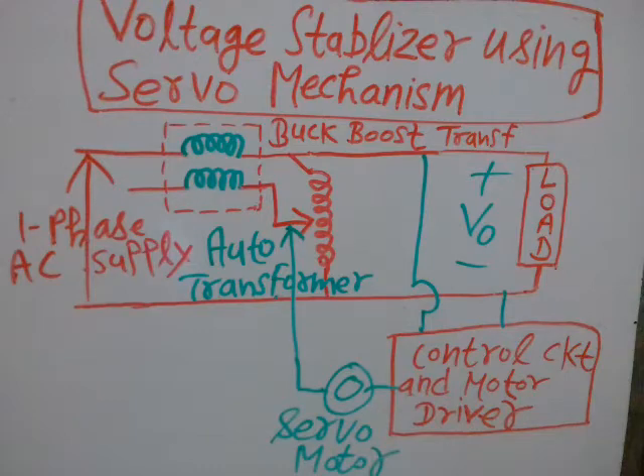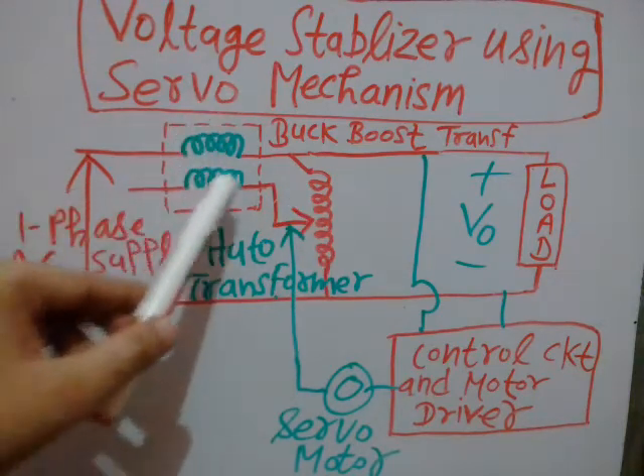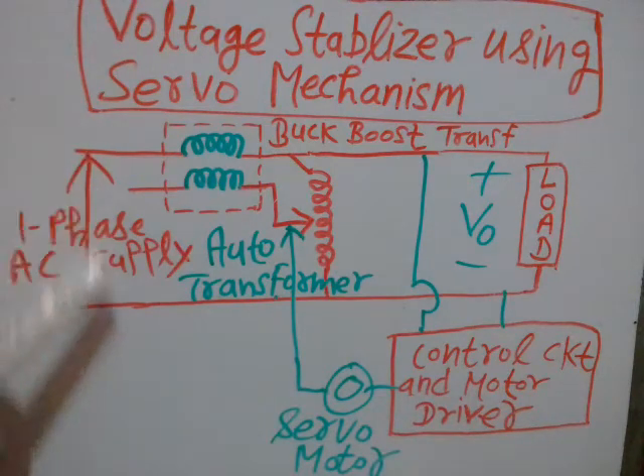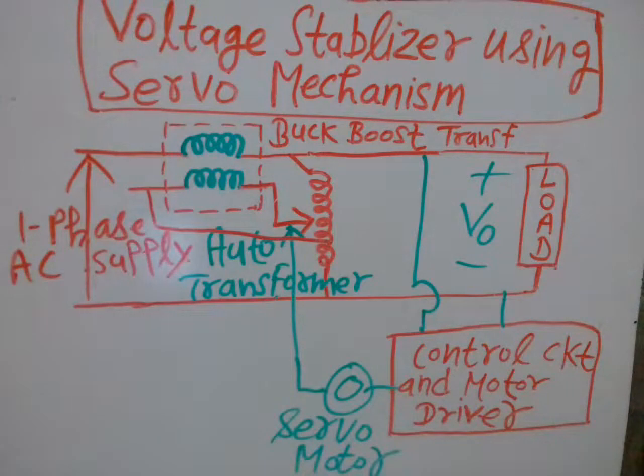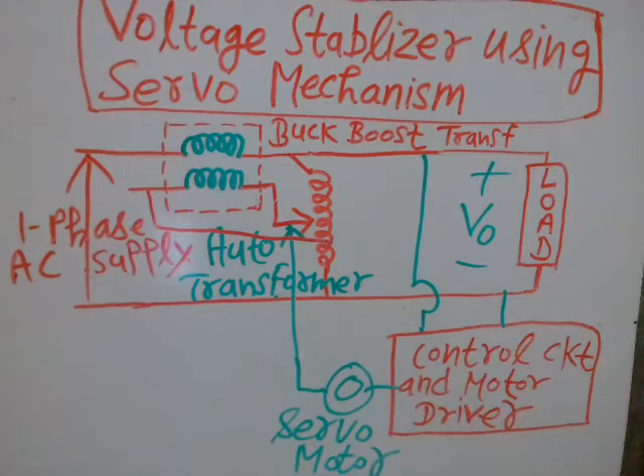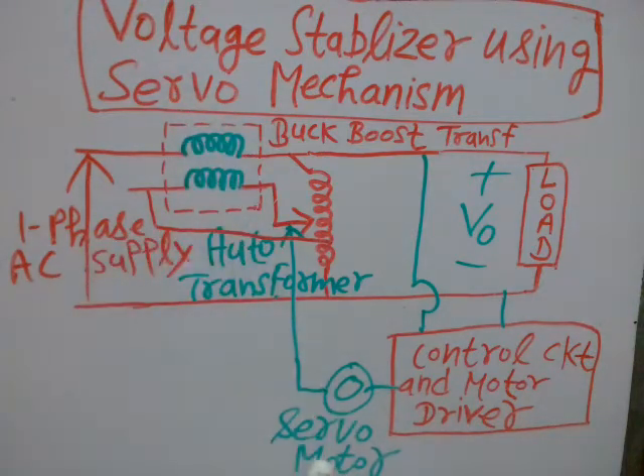This is the auto transformer connected here — this is a buck-boost transformer — and this is the single-phase AC supply coming in. In an ordinary stabilizer, a relay is connected, but here no relay is used at all. This circuit is free from any relay and instead uses a servo motor and auto transformer combination with a buck-boost transformer to fix the voltage across the load.